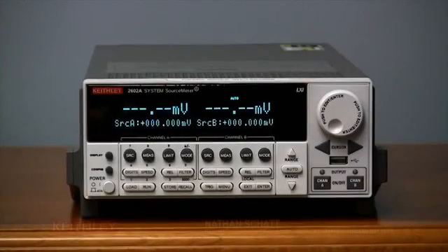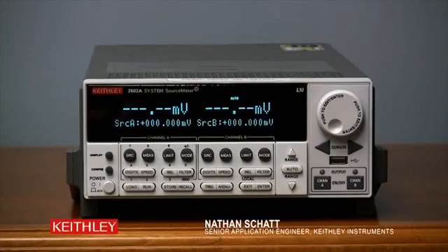Hi, this is a basic demonstration of using a 2-channel 2600A series System SourceMeter unit from Keithley to characterize a MOSFET. We will generate a family of curves using the internal web page, the TSP Express software in that internal web page, connected to via Ethernet. This is a useful application for people in the semiconductor industry, university researchers, and other customers.